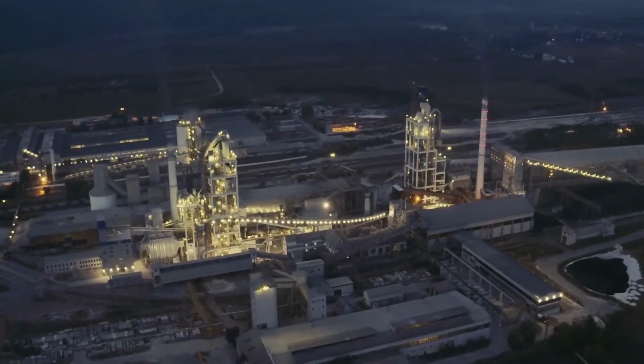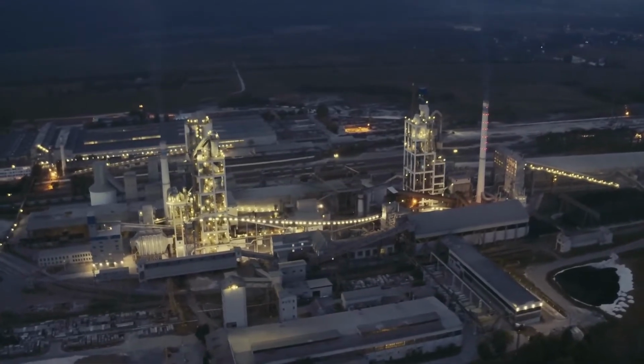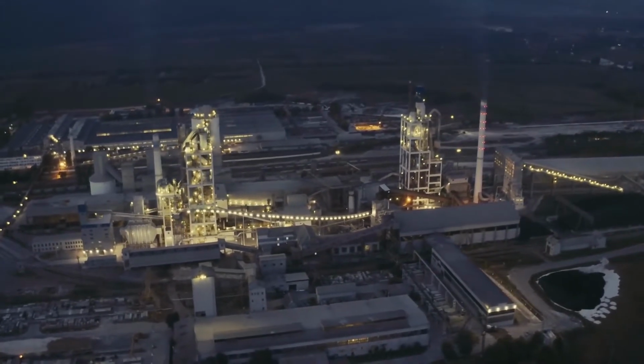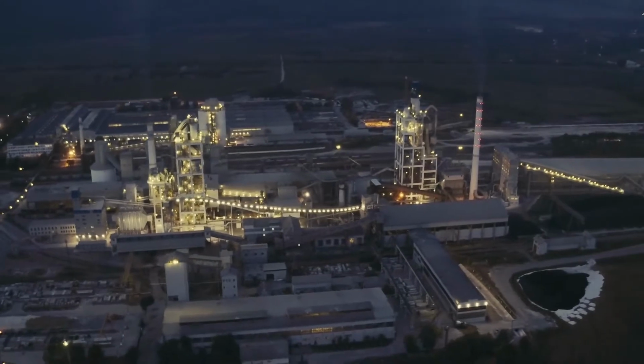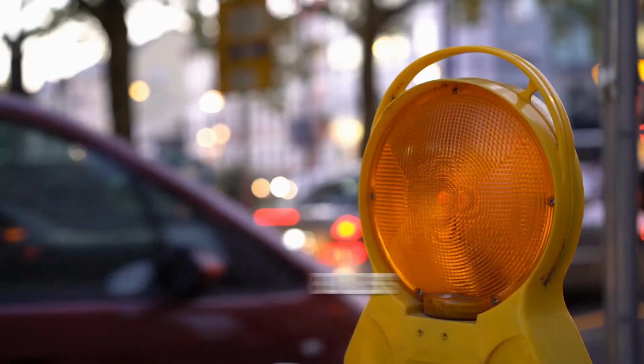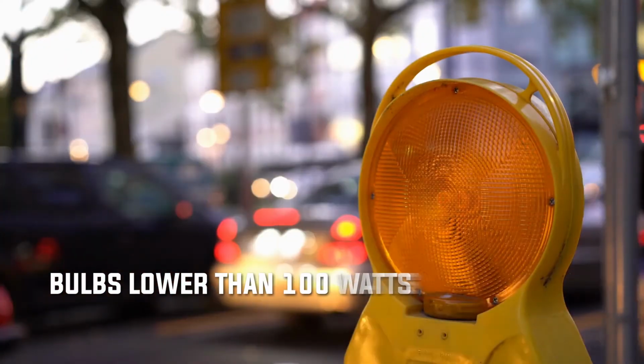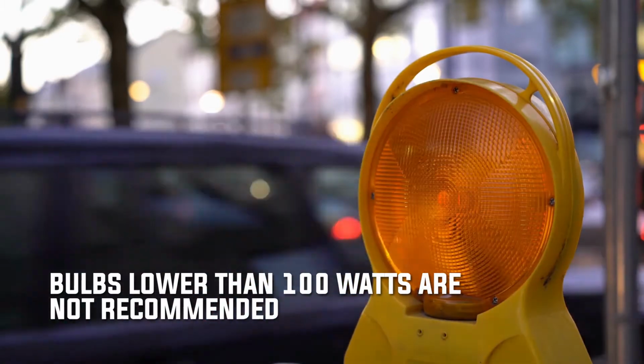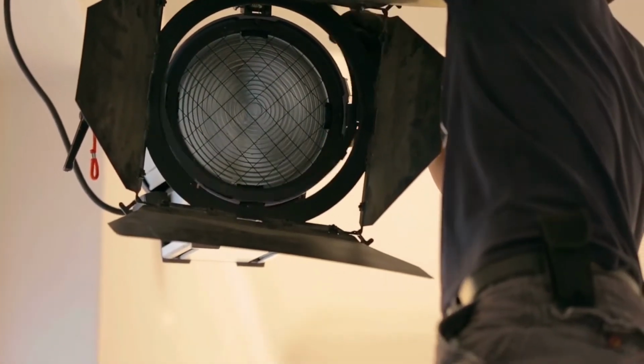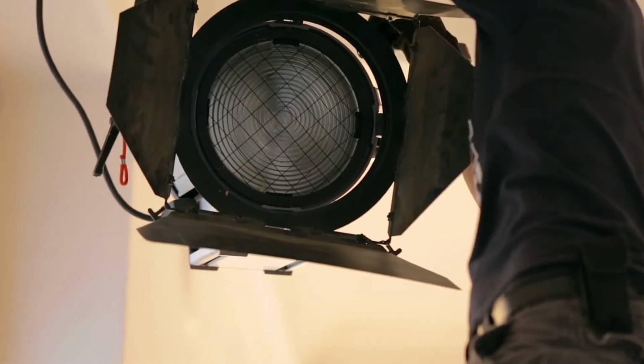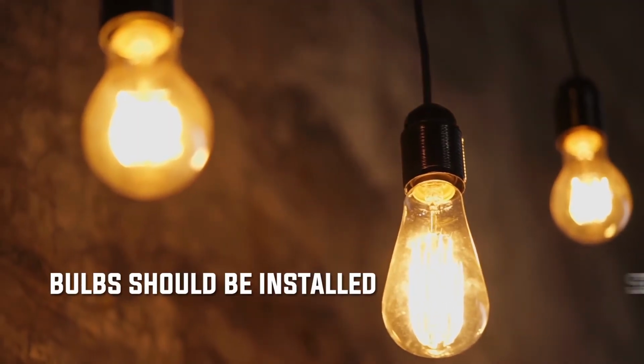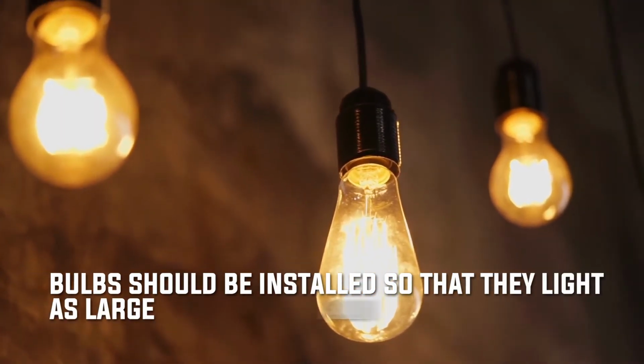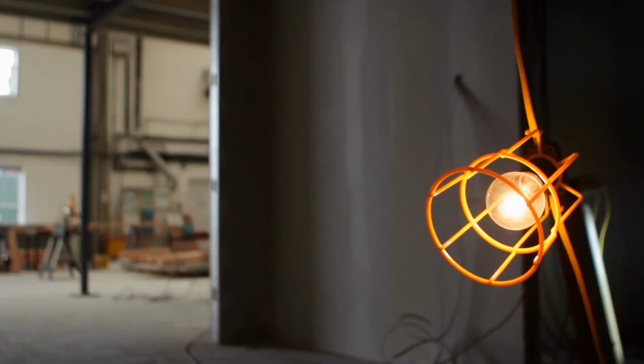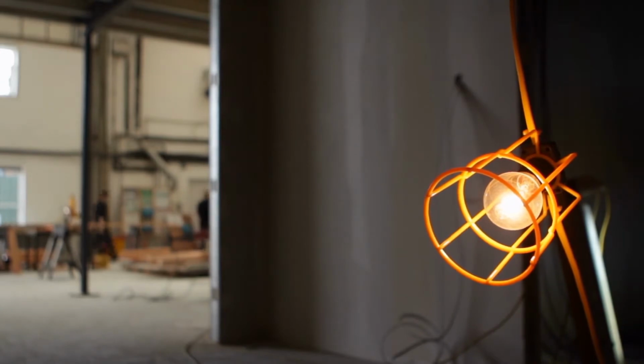Light should be at least 2.4 meters or 8 feet off the floor. Do not hang lights by the cord unless they are designed that way. Bulbs lower than 100 watts are not recommended. However, if bulb wattage is too high, it may melt the plastic cages. Bulbs should be installed so that they light as large an area as possible. They should also be protected by cages to guard against accidental damage.